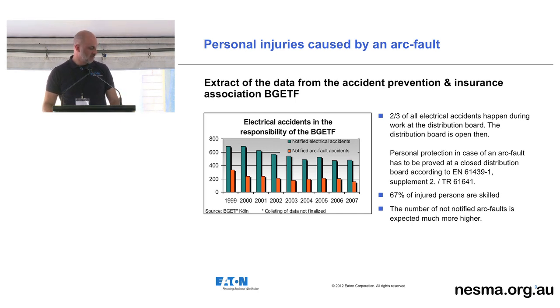So in the green, the taller bar there, is the number of reported accidents. In the orange, you have the ones that are due to arc flash incidents. This is taken from German data, but if you read statistics on the internet, in the US there's 5 incidents a day. This is quite a prevalent thing. So with all the best intentions on working on a board, or the way the board has been built, or having arc fault containment testing, it's all great and well, but as you see by that data, the greater majority includes arc flash. A great majority of those people were skilled or qualified persons working on a switchboard.